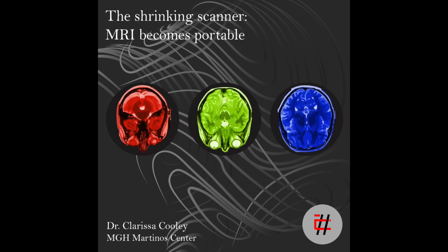Yeah, I think the use of permanent magnets has the major advantage of, number one, not requiring power, and number two, not requiring cooling. So the superconducting magnets require cryogenic cooling with liquid helium, and that has been a problem in the past. So I think that's definitely an advantage of this system. I think that there are also new designs out there that use high temperature superconducting magnets that also help with this problem. And also scanners, I think, are becoming better at not boiling off helium, so they don't need to be refilled as often. But yeah, I think this is a non-issue for permanent magnets.